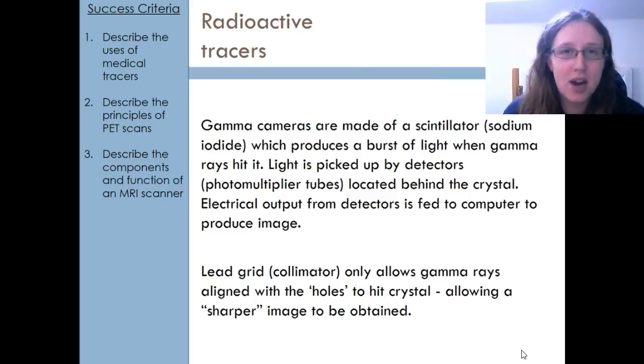In order to focus the gamma rays so that we don't just end up with light hitting everywhere, we have something called a collimator. This is basically just a grid of very long lead tubes that only allows gamma rays that are directly lined up with the tube to hit specific parts of the crystal. It removes the background noise so that you can focus in on the picture.